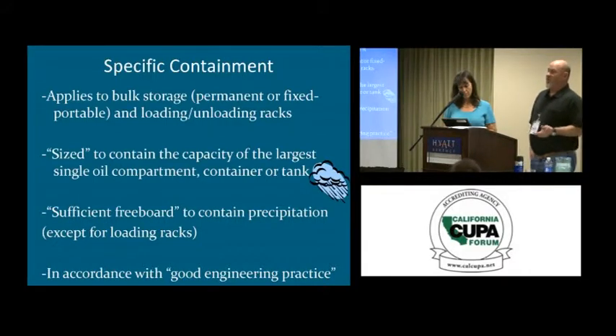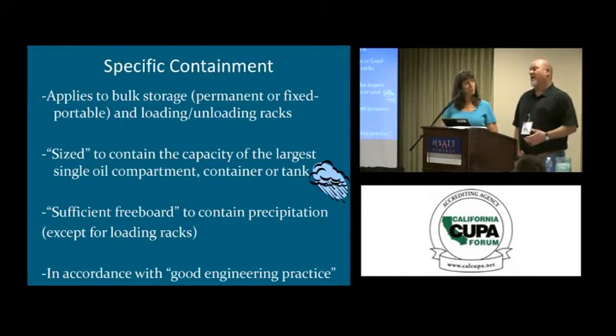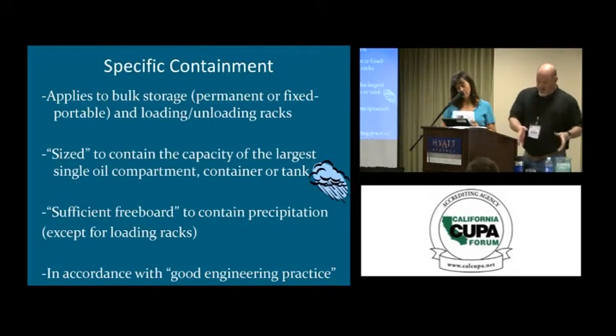We've got some significant challenges in the Hawaiian Islands right now, and we're working with a lot of facilities that were formerly saying, if we had a spill into our containment, we'd be able to clean it up because we have operators that are around or can be on site with response contractors. Well, it's a lava porous base setup over there, and some sort of asphalt or concrete or, in fact, poly liners are probably going to be a lot better off than just a dirt basin and hopefully an operator control. We had a facility overfill a tank by 14,000 gallons. It hit the ground and percolated in. Within an hour, they lost 13,500 gallons.